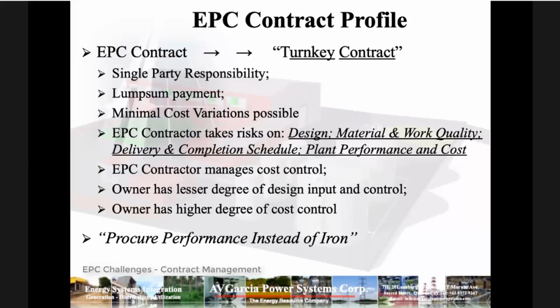Again, that cable, topic kanina: what is the size of the shielding? Kailangan ng concentric, full shield yan na sinasabi nila, mahal yun. Now, it's up to you, the engineer, to make sure that your shield is not going to be burned. So how do you do that? You go back to your short circuit calculation to determine, to predict, sabi niya kanina, may predict yung short circuit, yung fault current na dadaan sa shield. Because you need to define that. In fact, it is the duty and the responsibility of the engineer to define the maximum allowable line to ground fault that you will allow in a system. Responsibility mo yun. It's part of EPC.